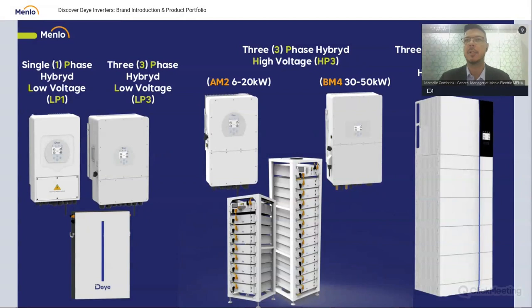An overlook on the hybrid systems and how they look. On the left-hand side, we've got the single-phase hybrid low voltage inverter with the Deye low voltage battery. Next to it, the three-phase low voltage inverter connected to the same battery. Then three-phase high voltage, with two ranges: the 6 to 20, and the 30 to 50. We've also got pictures of the racks: an 8-battery rack on the left, and a 12-battery rack on the right. And last but not least, the all-in-one high voltage inverter system, three-phase, which looks really good.